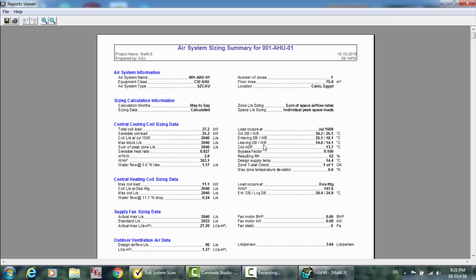Okay, the leaving dry bulb, wet bulb, this is the supply temperature that leaves the cooling coil. It is at 14.8. Okay, and here the coil apparatus dew point is 13.7. It is lower than the supply due to the bypass factor. You know, if the bypass factor is at the lowest value here, 0.05, this temperature will increase, and the resulting RH here is the relative humidity inside the zone. It will be 52%.